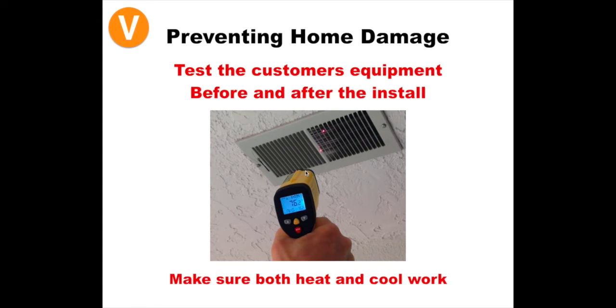All right, so now we're going to talk about preventing home damages. The first step when it comes to preventing home damages is testing the customer's equipment. You can see in this picture that we have one of these infrared thermometers. It sends off a little laser, and you can actually read surface temperature on certain things. In this case, they're reading a temperature off of a heating and air conditioning vent. Now, in all of your toolkits, you're going to be receiving one of these thermometers. And we want you to be able to use these because in some cases when you go into a customer's home, and I've heard of a lot of technicians doing this, they walk in, they put their hand by a vent, they feel air, and they automatically assume that since they feel air, it's working. But they haven't confirmed if that air is warm or if it's cold. It's just air. And so in that case, maybe the fan's working, but maybe something's wrong with their system and the system's not working correctly.